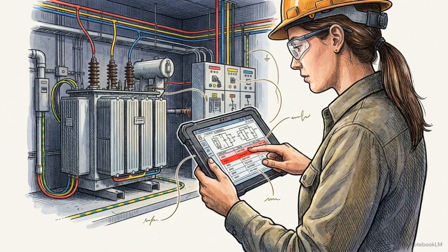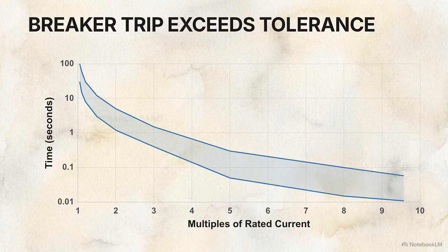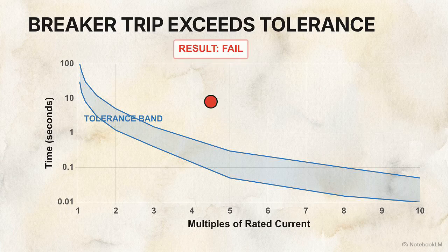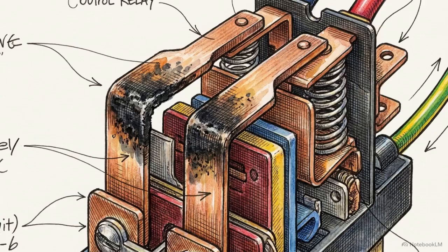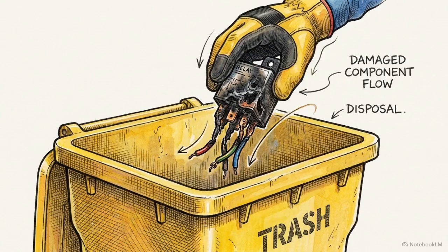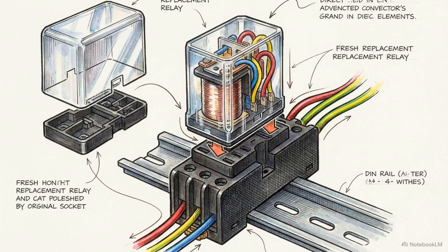Effective commissioning requires the engineer to actively hunt for data deviations rather than simply recording results. If a breaker exhibits a delayed trip or a nuisance trip outside of the strict tolerances of a specific curve, it fails. There is no middle ground. Control logic deviations face the same zero-tolerance policy. If a relay chatters or its contacts stick, recalibration is not an option. The physical relay must be discarded and replaced.